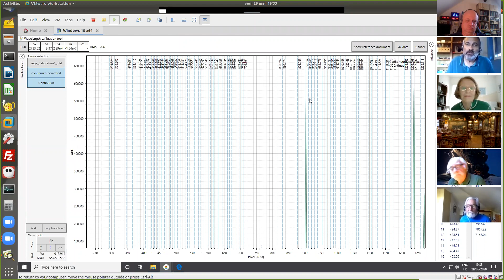So a very simple way to see if there is a problem somewhere is just to look. For instance, I can go to this line here, the 5,852 line. At this position, if I look at where this line is, well, I selected it because this is the big one here in the middle of the spectrum. And then I know that this is this line. So in this case, I can see that it is properly detected. If I zoom on it, I can see that it is properly detected, at pixel position 902 in this case.